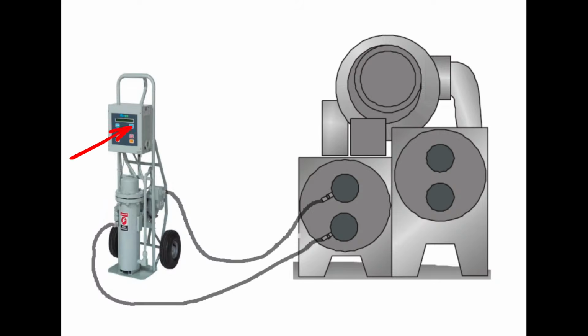So this machine can wire in multiple voltages in various ways. You can tie it into the actual chiller's control or input panel, whatever the case may be. The whole point of this is to pressurize the machine up above a negative pressure specifically. With a low pressure machine, part of the whole definition is that these machines operate below atmospheric pressure, especially on the evaporator. And when these machines are in an off state, they will typically sit in a vacuum, even if it's negative 1, 2, 3 psi below atmospheric. And that's gauge that I'm speaking in.